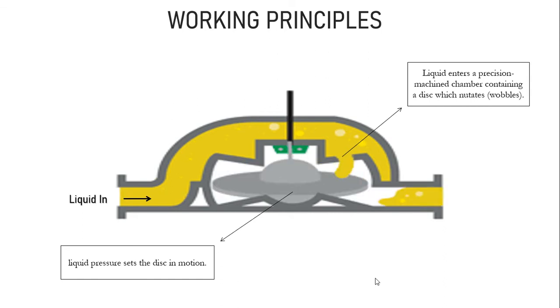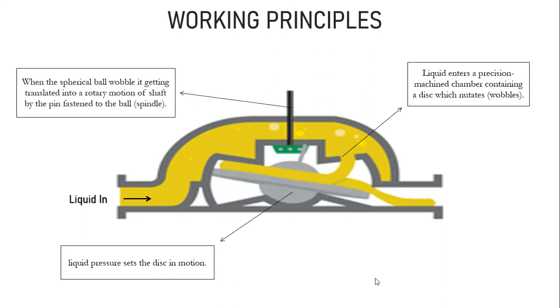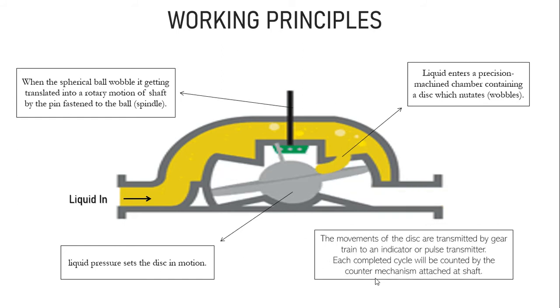Liquid pressure sets the disc in motion to make a complete cycle. The spherical ball wobble is translated into rotary motion of a shaft by a pin fastened to the ball. The movement of the disc is transmitted by gear train to an indicator or pulse transmitter. Each completed cycle is counted by the counter mechanism attached to the shaft, and lastly, the liquid exits the device at the right side.